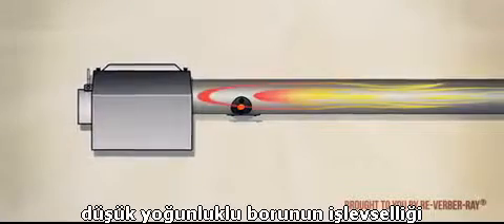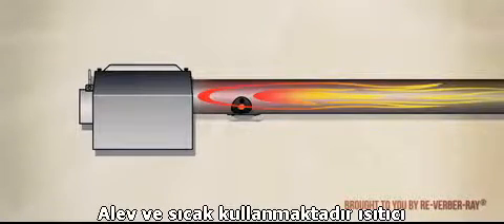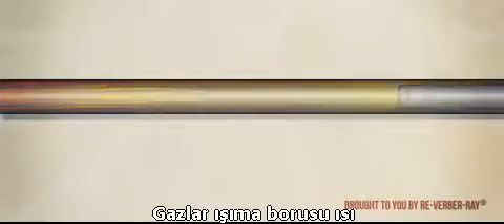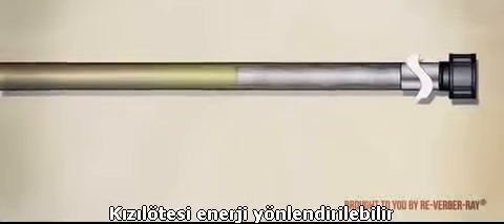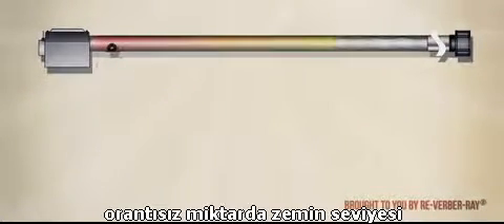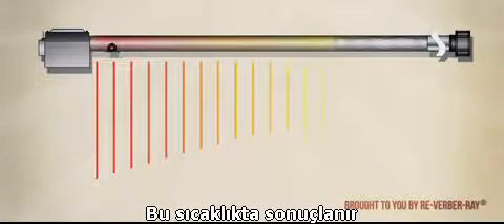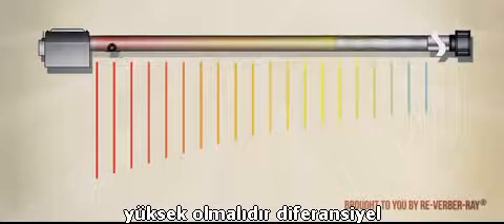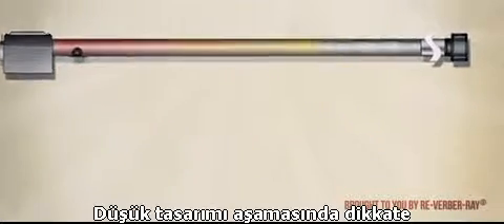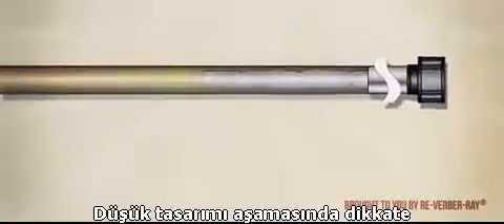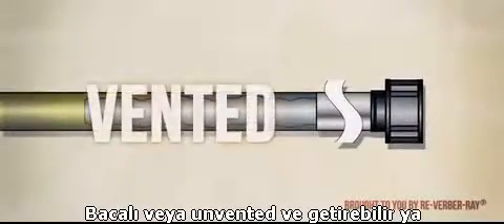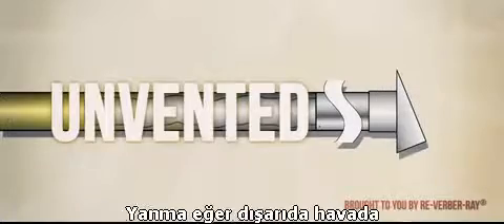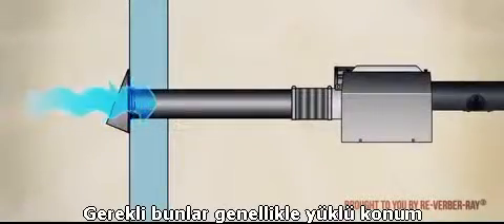Due to the functionality of a low-intensity tube heater, which utilizes a flame and hot gases to heat the radiant pipe, the infrared energy can be directed to the floor level in a disproportionate amount. This results in a temperature differential, which should be highly considered during the design phase. Low-intensity heaters can be installed either vented or unvented and may bring in outside air for combustion if necessary.